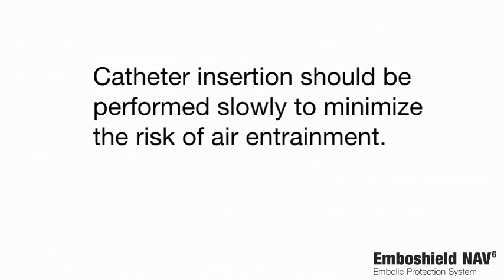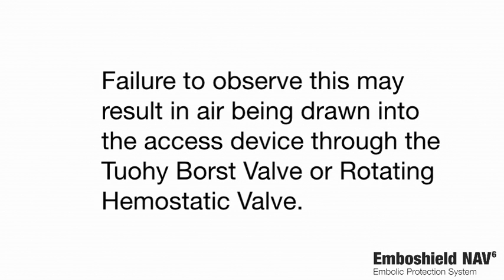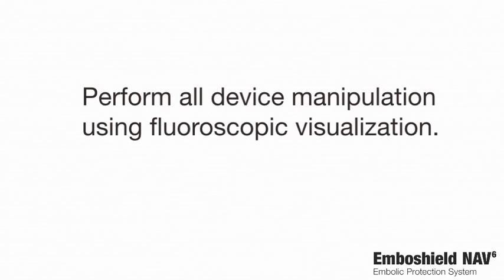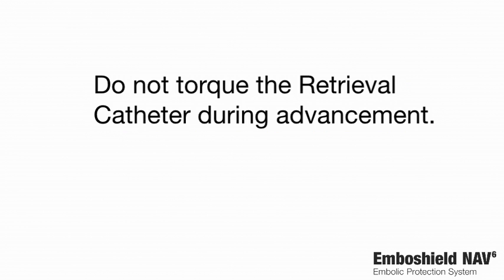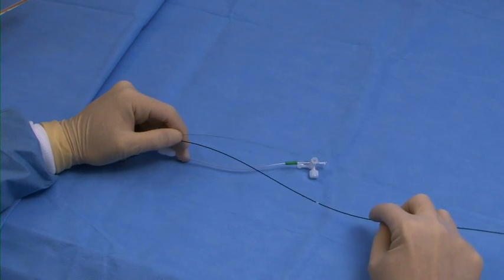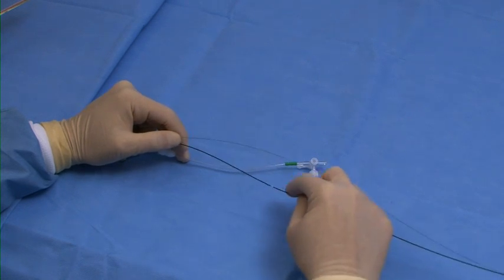Filtration element retrieval. Catheter insertion should be performed slowly to minimize the risk of air entrainment. Failure to observe this may result in air being drawn into the access device through the Tuohy-Borst valve or rotating hemostatic valve. Perform all device manipulation using fluoroscopic visualization. Do not torque the retrieval catheter during advancement. Advance the retrieval catheter over the bare wire.